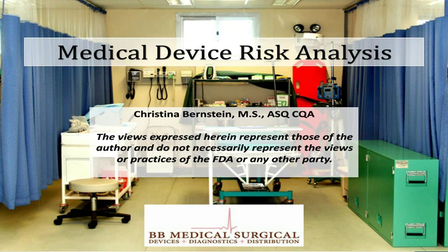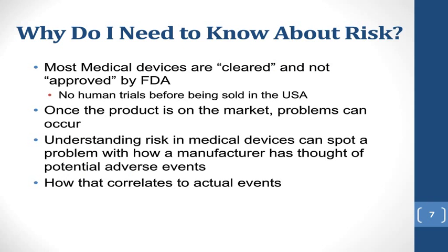The reason is that the concept of risk is a little bit different with medical devices as opposed to if you thought about risk in the financial markets or risk in maybe a psychological sense, someone being like a risk taker or risk averse. But one of the reasons that it's so important to understand this stuff is that most medical devices that are out on the market in the United States, they're cleared by the FDA and they're not approved. And the difference is that there's no human trials, there's no clinical data in a lot of these devices.